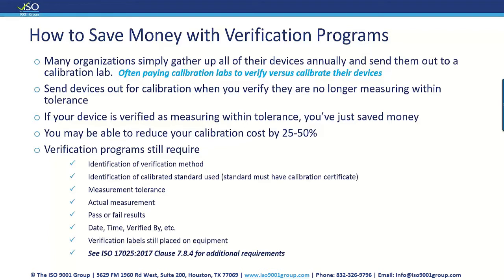You should identify what the measurement tolerance was, the plus and minus, the range. You should document the actual measurement that the device gave when you did your verification. Did it pass or fail? You should list that on your verification record, with date, time, and who did it. And you still need to put labels on your equipment showing that it was verified and when it was verified, so people who are using the device can see that it was verified.